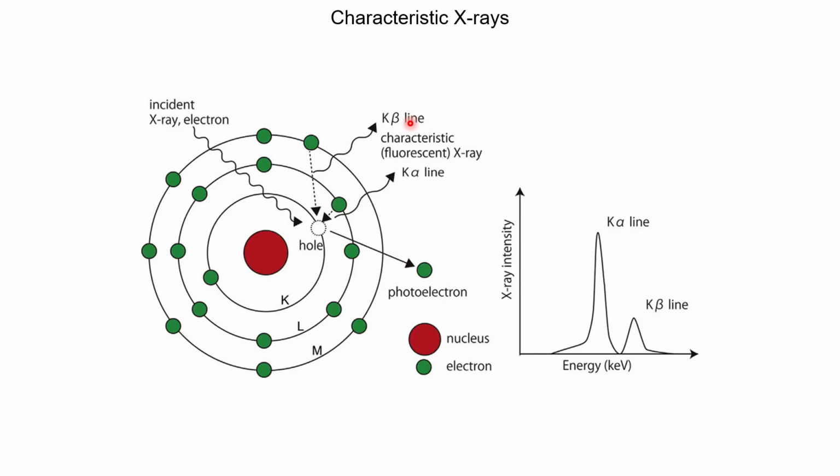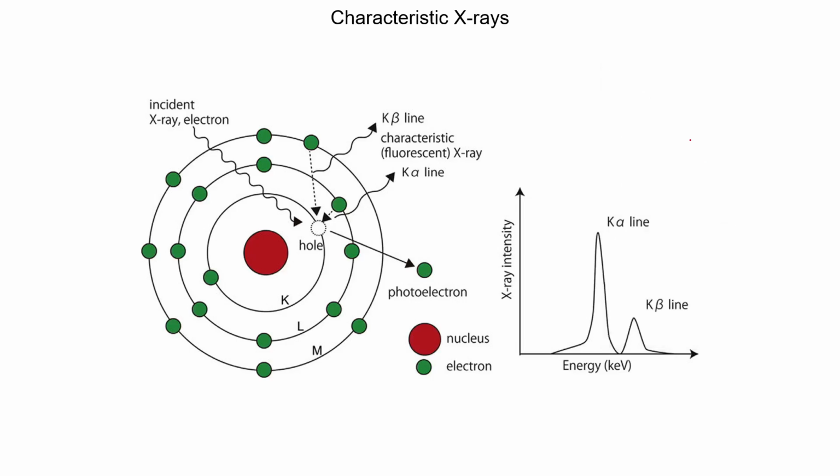If you have different kinds of atoms and you have selected the K alpha line for all, then you need to check that the different atoms don't have an overlap of the energy of the selected characteristic X-ray. Then you can select that only the K alpha line, or the K beta line, for this atomic number will be detected. And if your specimen has elements at different positions, then you can directly image them.